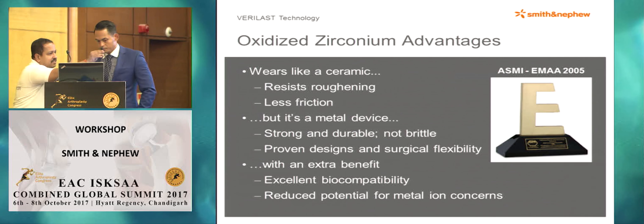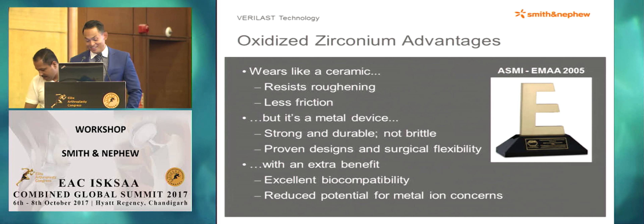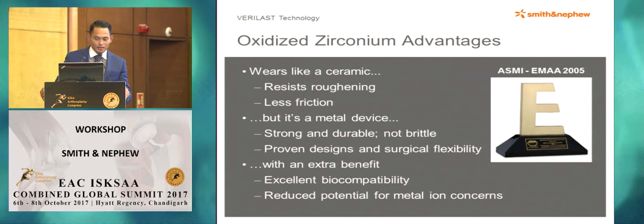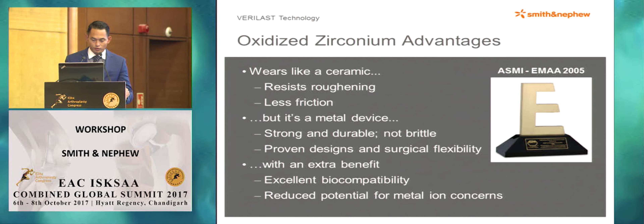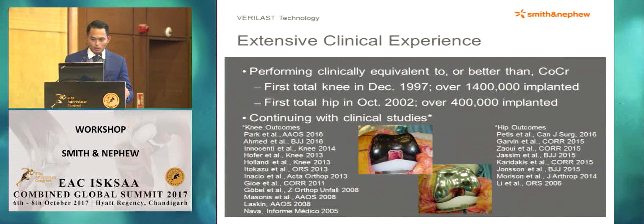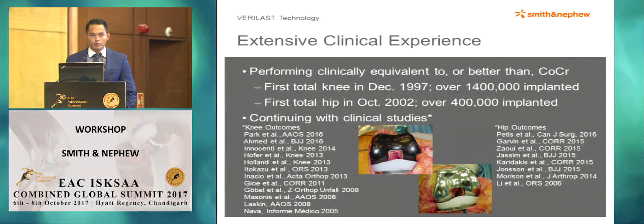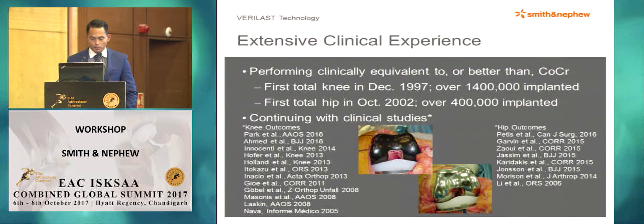In summary, the Oxinium advantages: it wears like a ceramic by resisting roughening, there's less friction, but it's a metal device so you don't have the concern about brittle fracture as you do with a purely ceramic zirconium head. The designs are proven, and flexibility is seen surgically with an extra benefit — there's excellent biocompatibility with reduced potential for metal ion concerns, as we learned from metal-on-metal bearings. There's extensive clinical experience: the first total knee was done in December 1997 with over 1.4 million implanted to date, and the first total hip was in October 2002 with over 400,000 implanted. Tried and true.